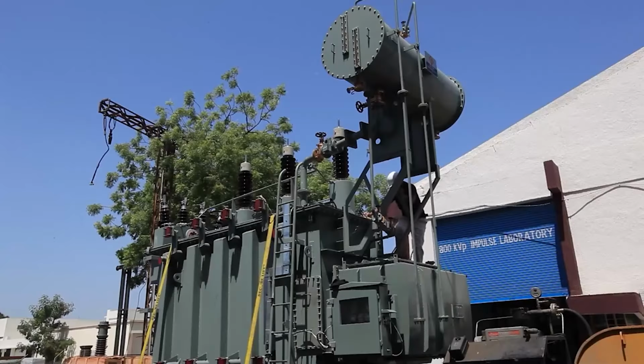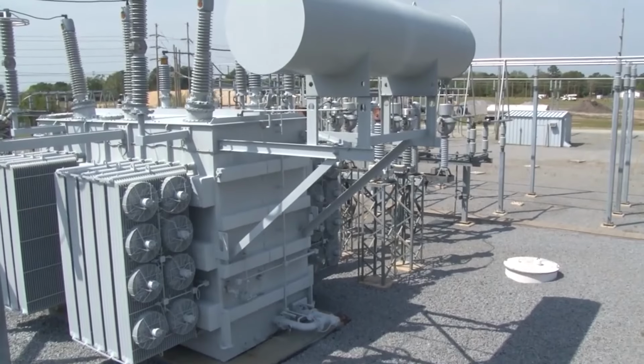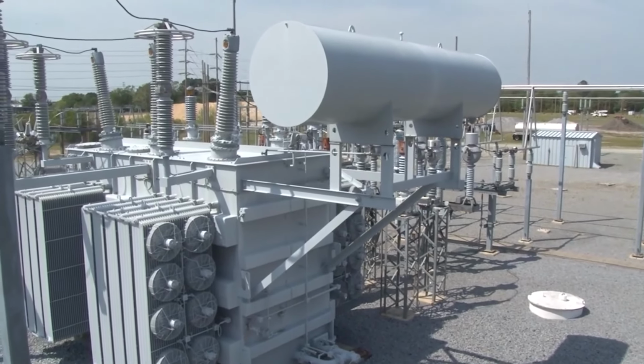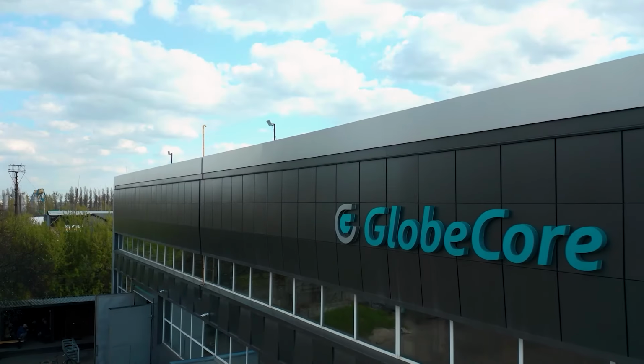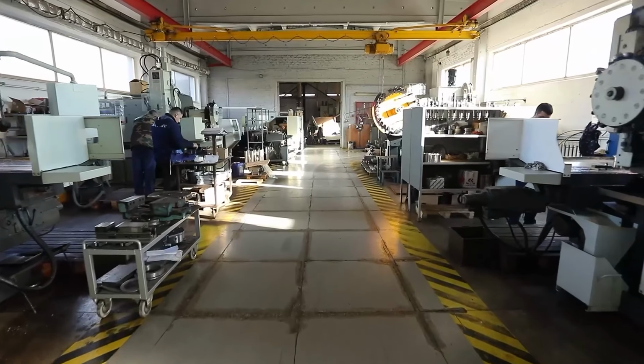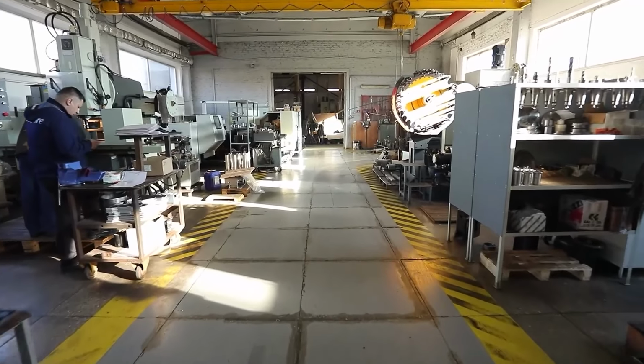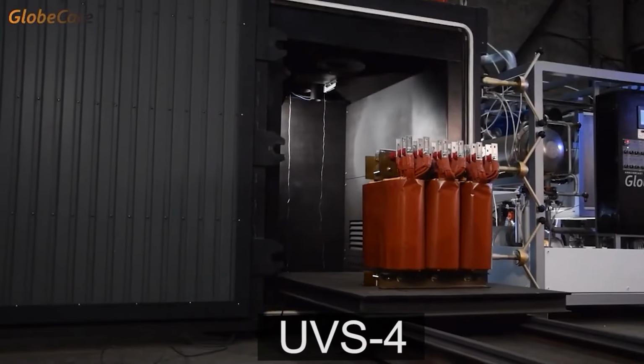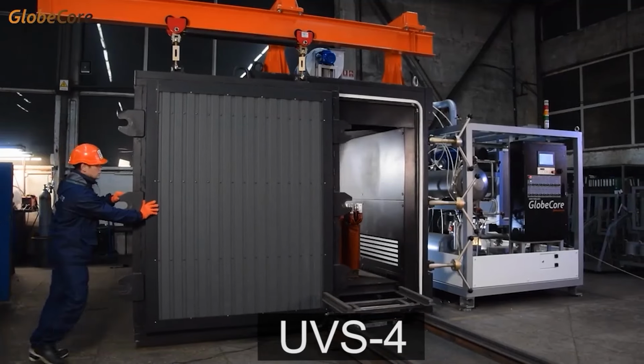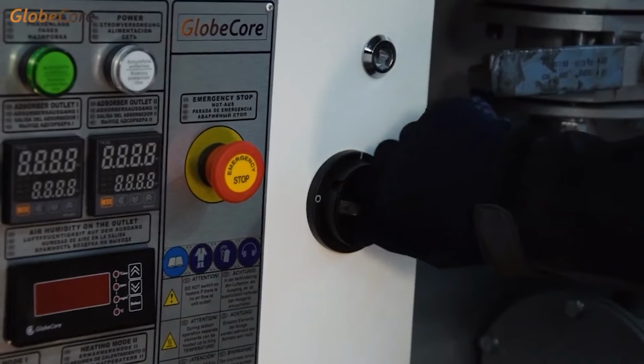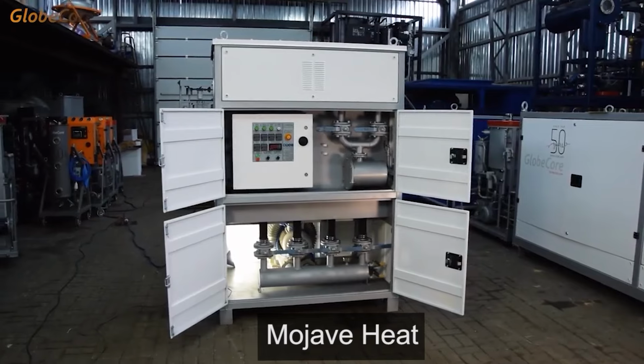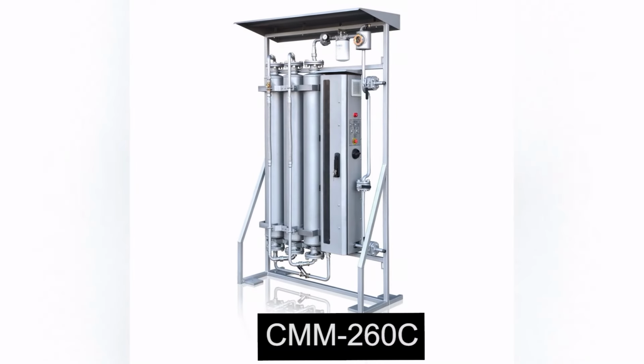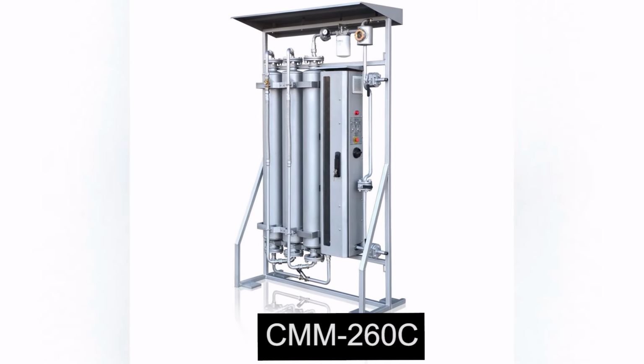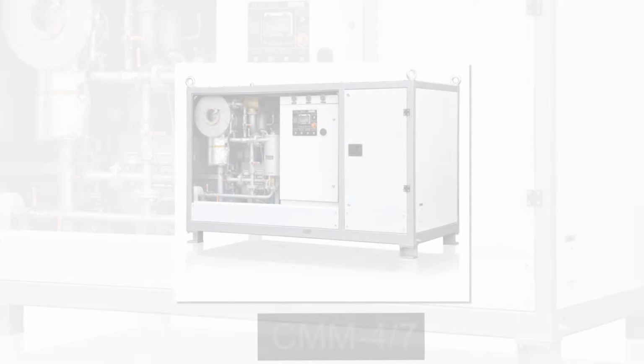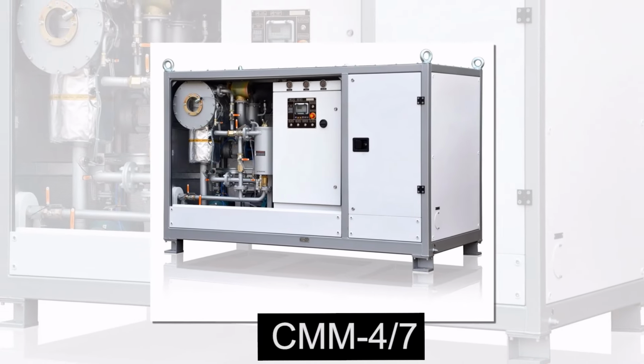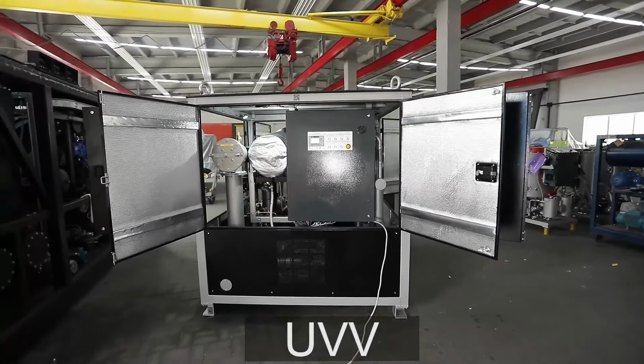Depending on where the transformer has to be serviced, the dehydration of the insulation is carried out with or without removing the windings. GlobeCore has developed technologies and equipment for drying the solid insulation of transformers, which are used in both cases. The insulation drying with pulling the windings out can be carried out in a vacuum oven. The insulation drying without pulling the windings out can be carried out using the hot air blower, the continuous transformer oil drying unit, the thermal vacuum dryer, or the vacuum water vapor freezing unit. We will show you in this video how the low-frequency heating method is implemented.